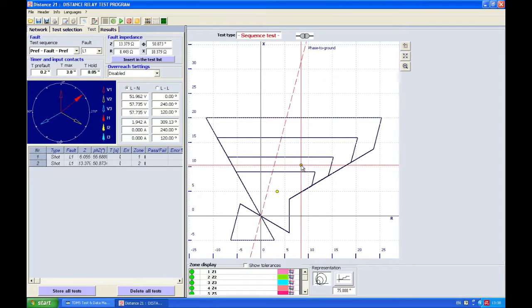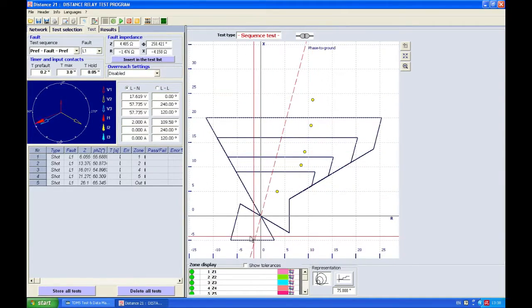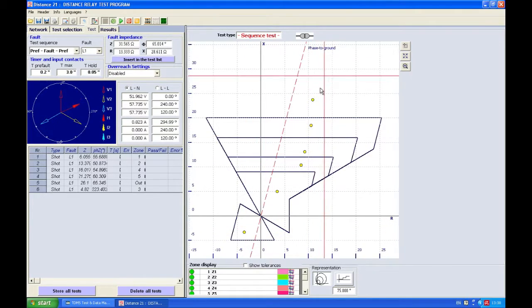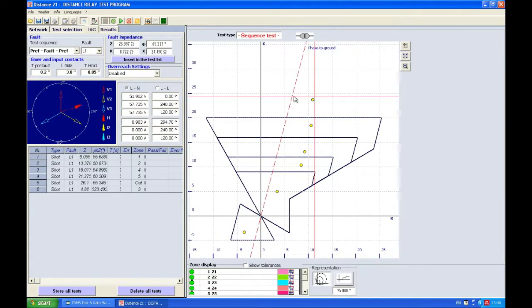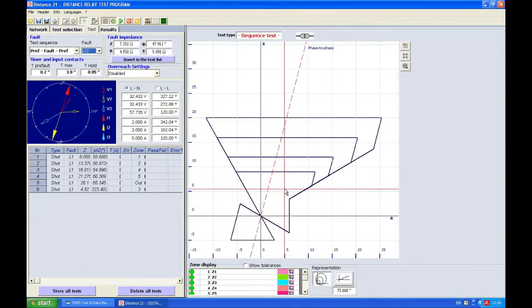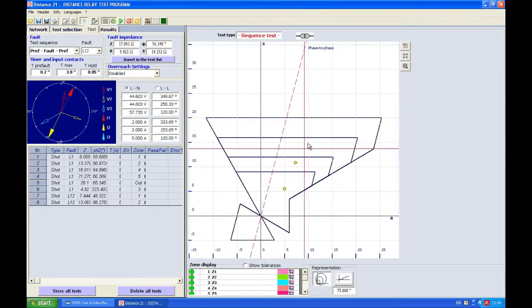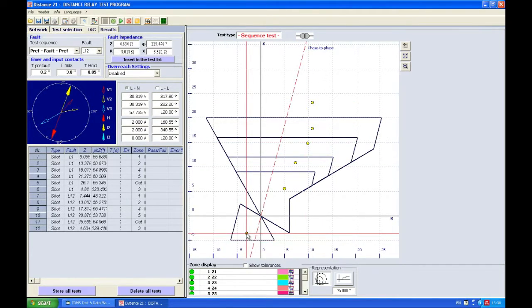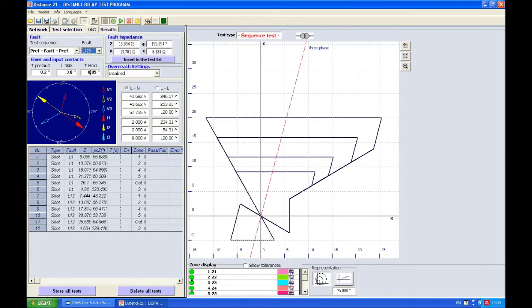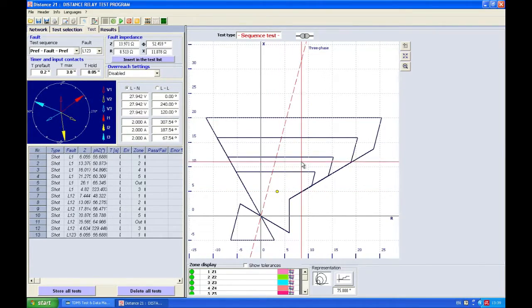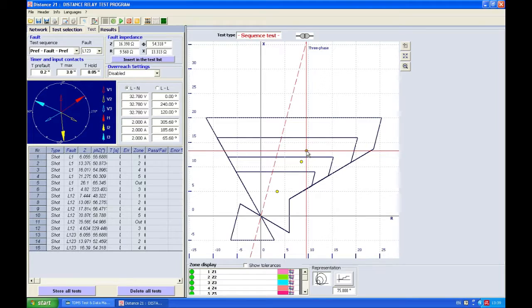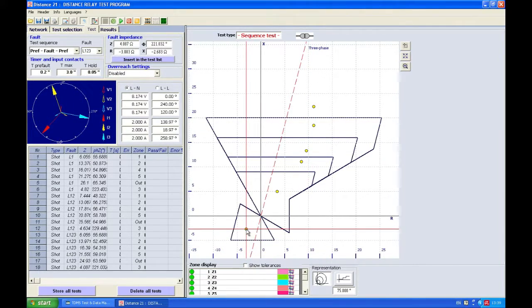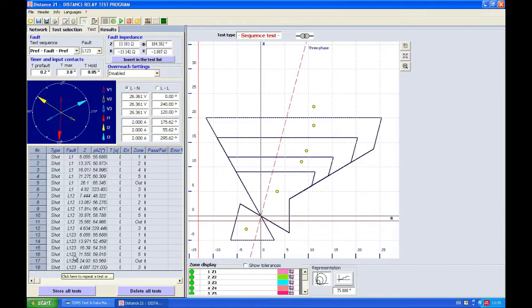So first I'm going to choose all the points which I want to test for my relay. So all the zones and of course outside for phase one, also for phases one-two, one-two-three-four outside and zone three. We're also going to do that same test for three phase fault. So one, two, three, four, five, six. So we have 18 tests now for phase one, phase one-two, and all three phases together.